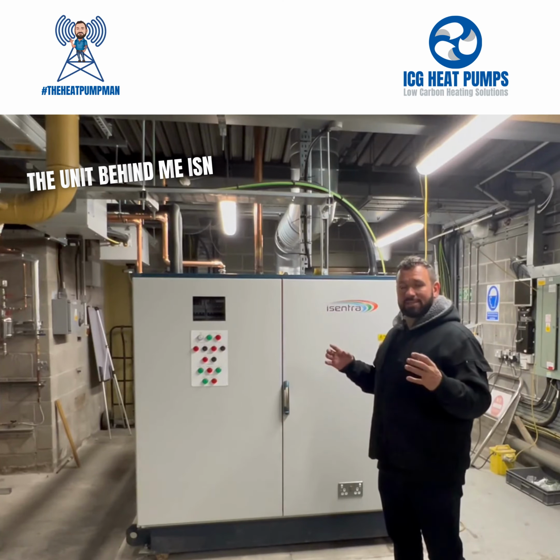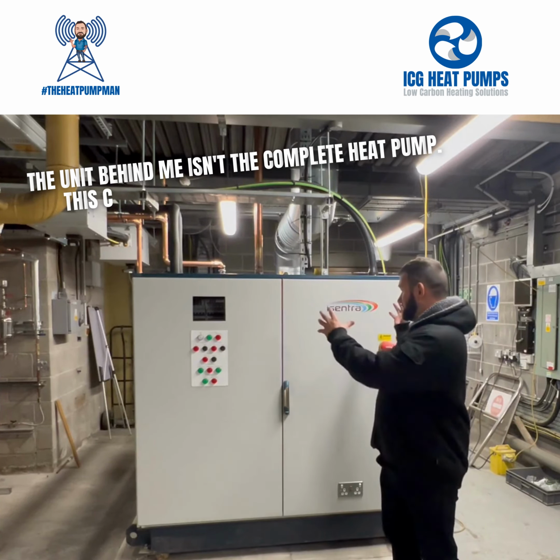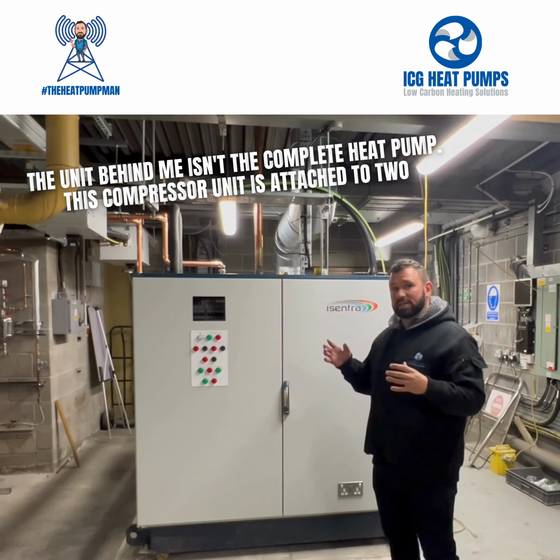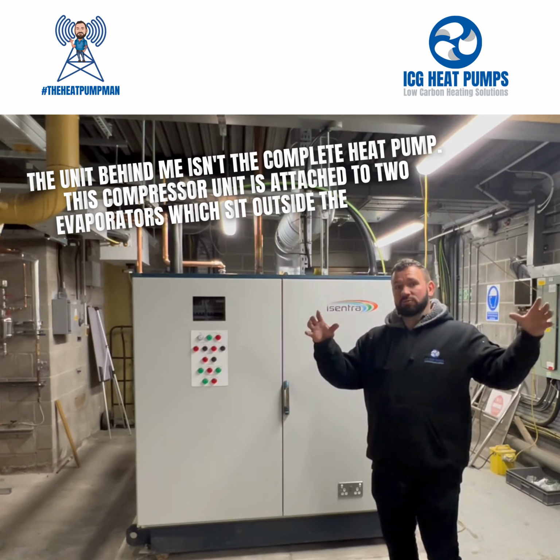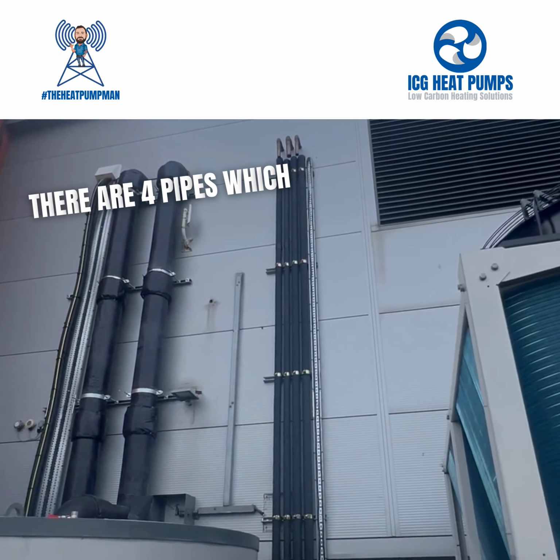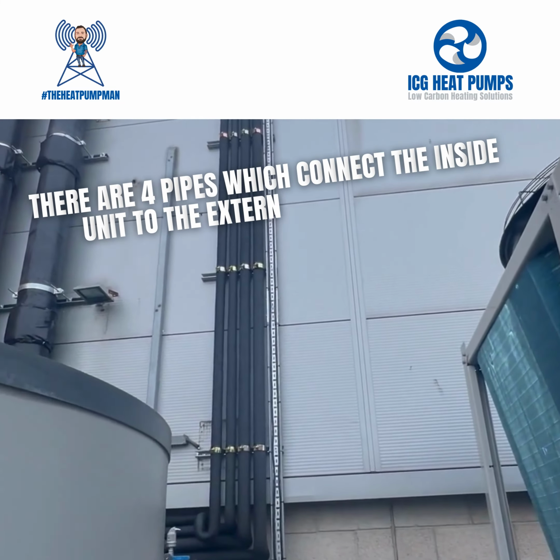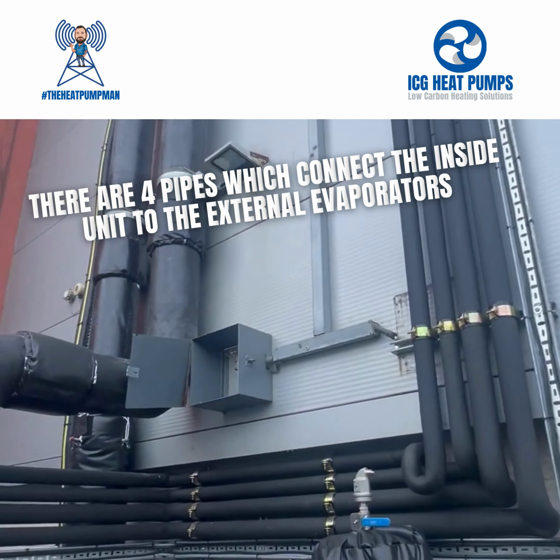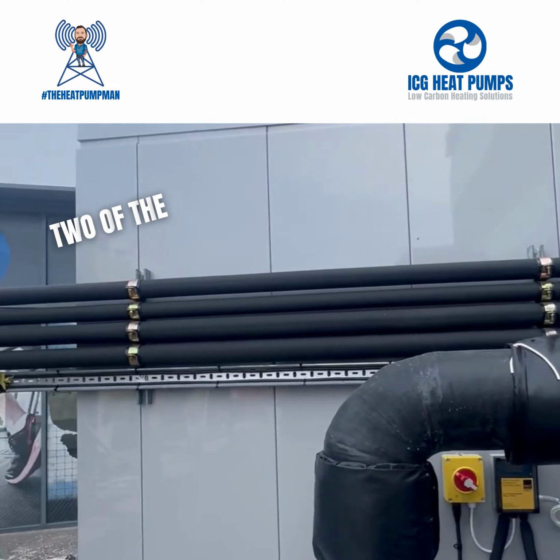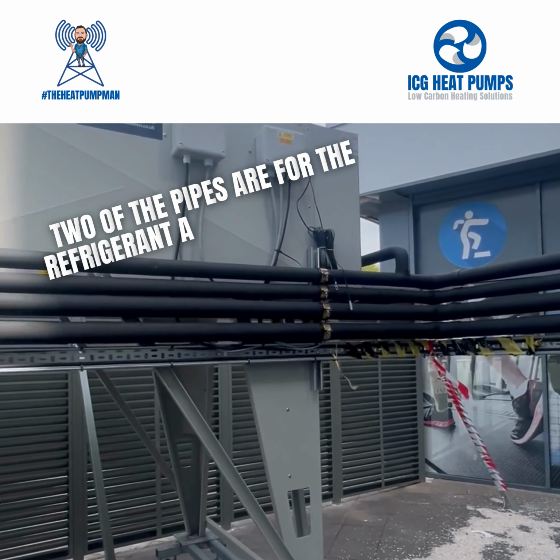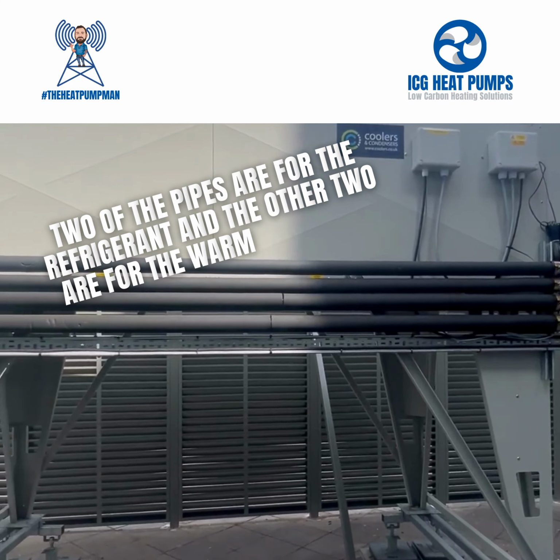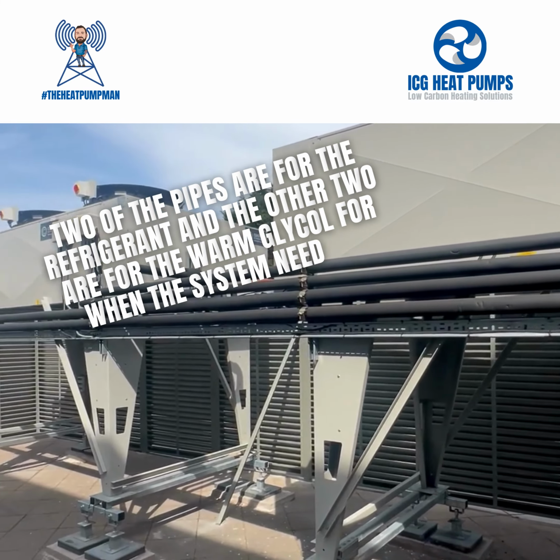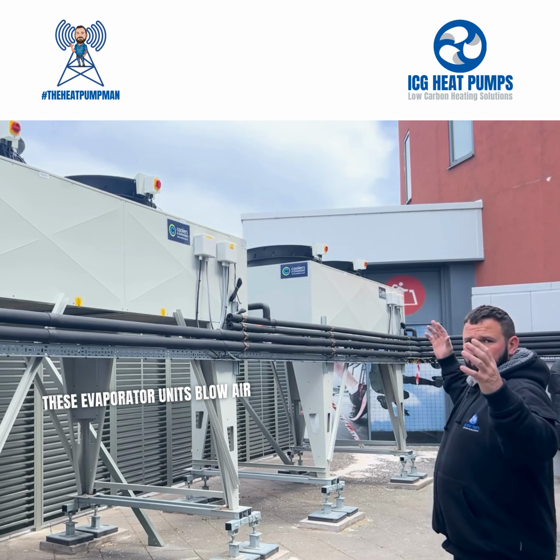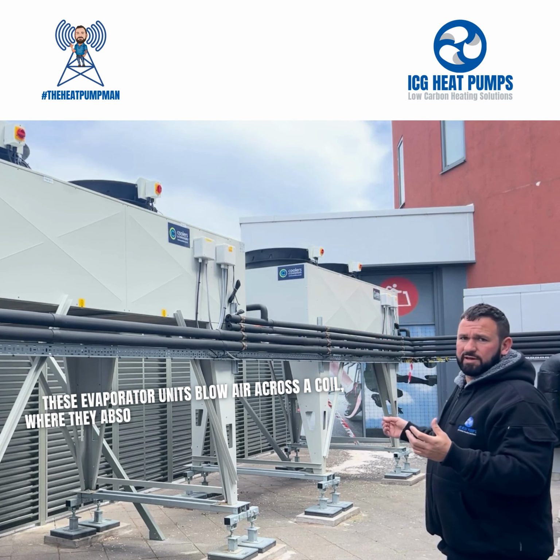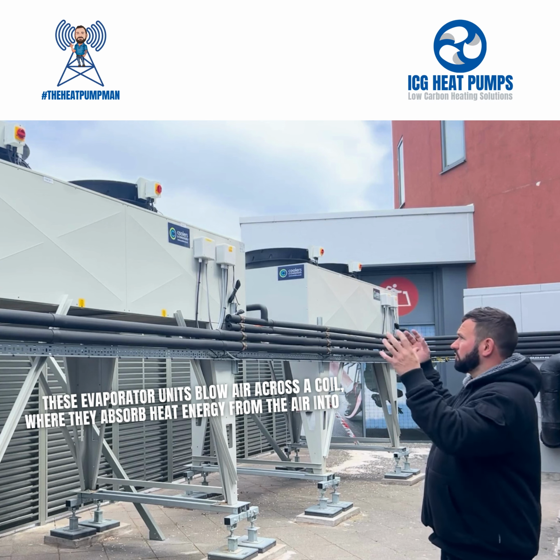The unit behind me isn't the complete heat pump. This compressor unit is attached to 2 evaporators which sit outside the building. There are 4 pipes which connect the inside unit to the external evaporators. 2 of the pipes are for the refrigerant and the other 2 are for the warm glycol for when the system needs to defrost.